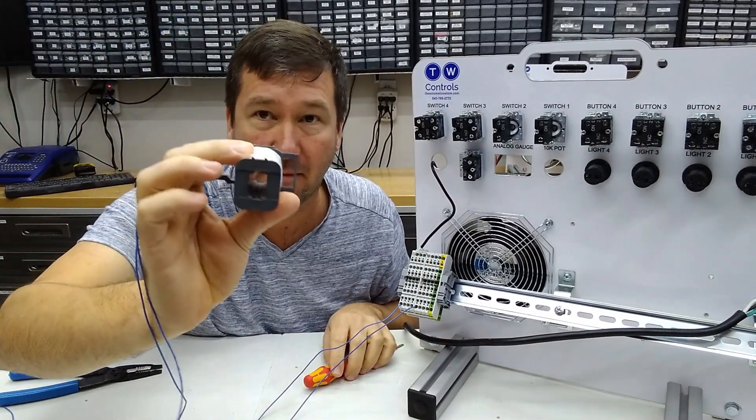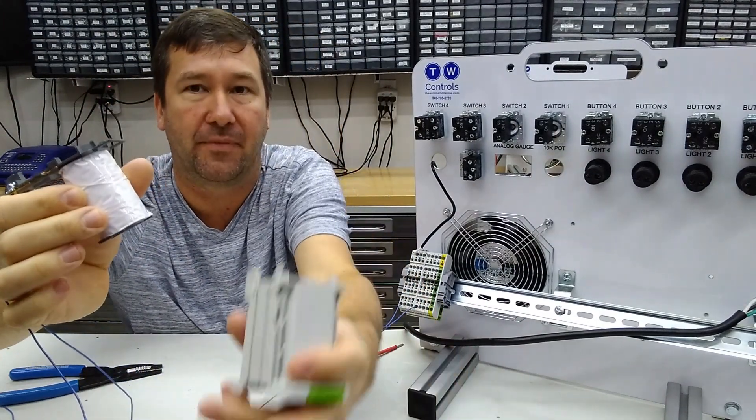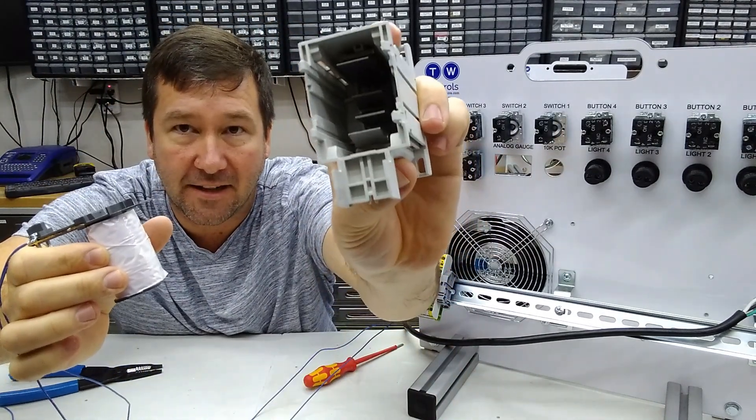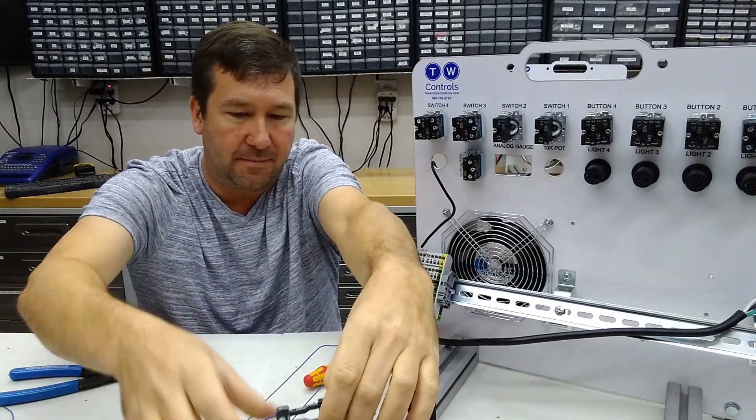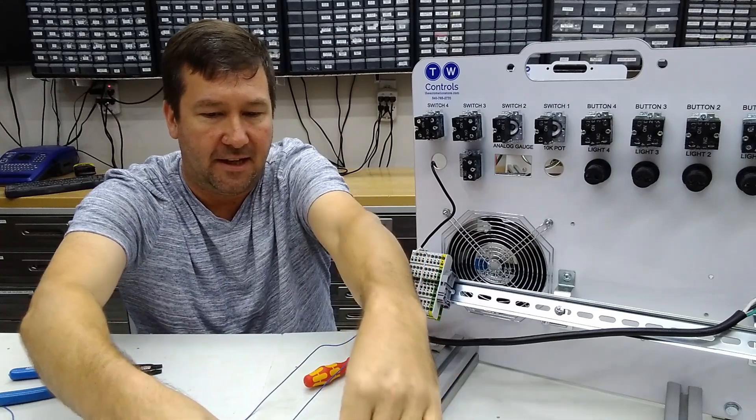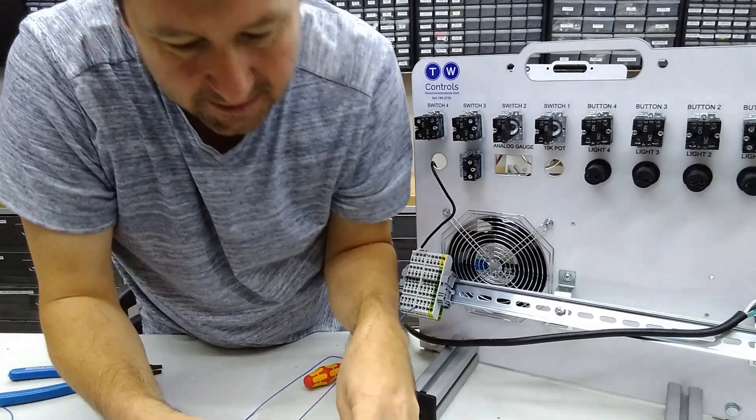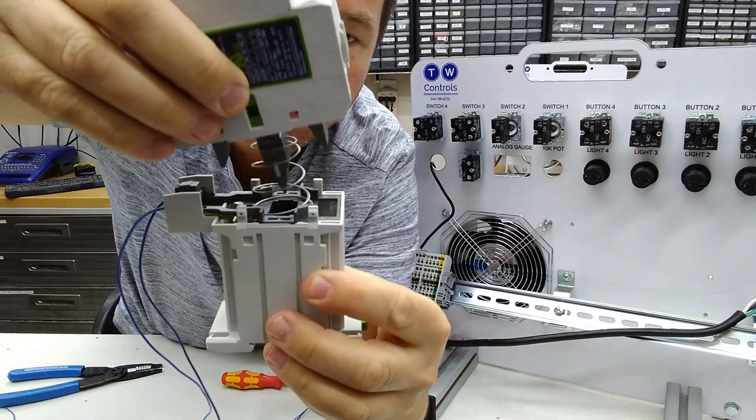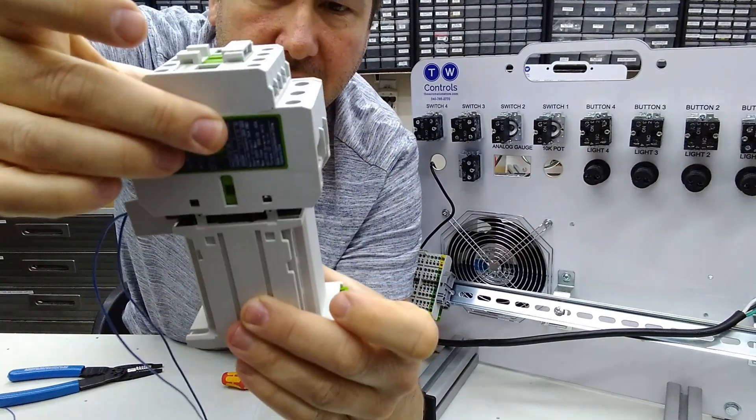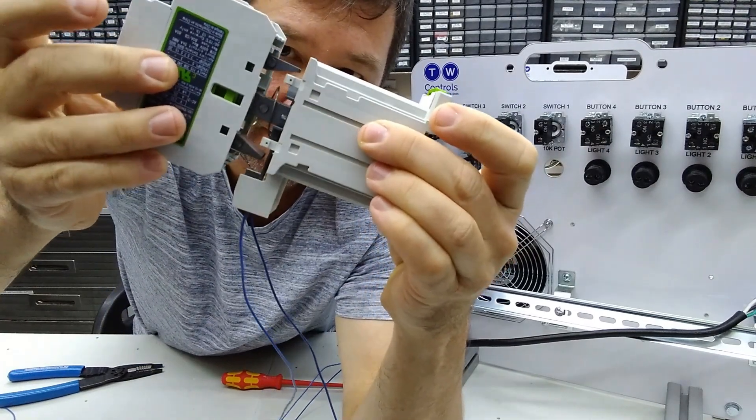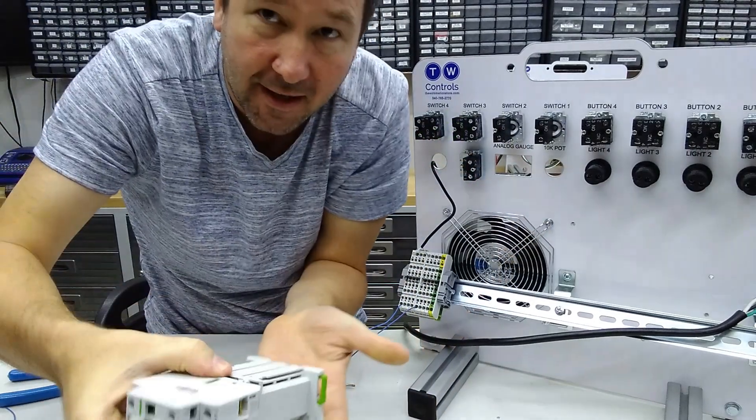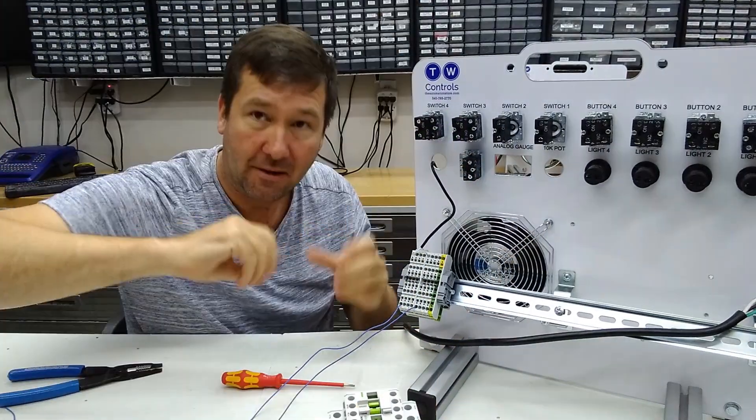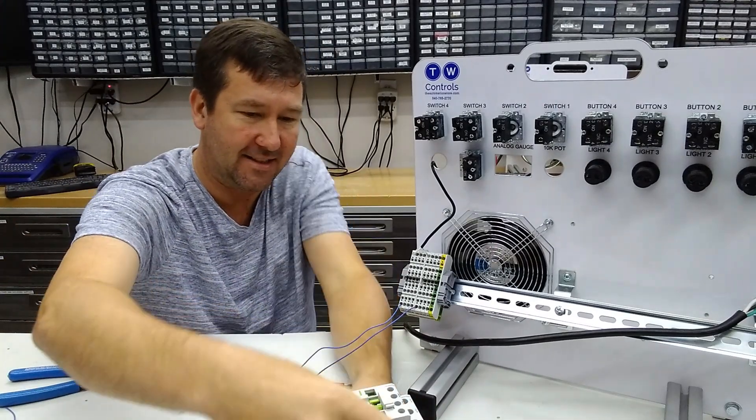So this is an electromagnet that is actually pulling this contactor in. Then you see in the contactor there's a big chunk of iron in there. And what that is going to do is make this magnetic field such that it's going to want to pull the other side in. So as we bring this contactor close, it actually grabs it right there at the end. And that's how a contactor or a relay works. Really it's an electromagnet that pulls those contacts in.